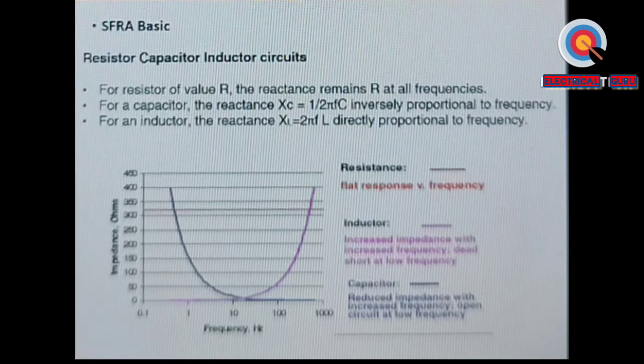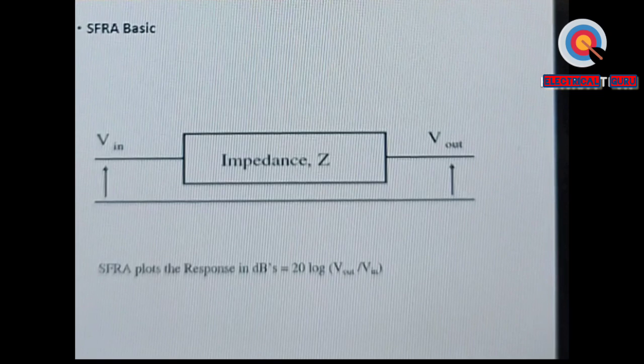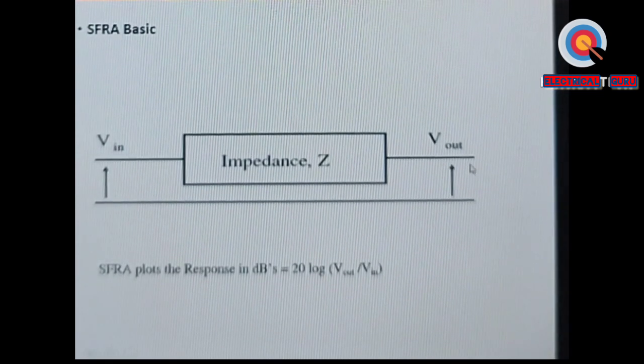So you now get the basic fundamentals with reference to frequency, except that R, XL and XC will keep changing, and that can be calculated or plotted in terms of a graph. So what we do is we have a V input, and we measure V output.